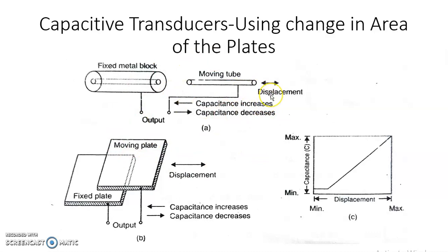As seen in the diagram, we are measuring the physical quantity displacement in terms of change in capacitance. In the first case, the parallel plates of the capacitor are in the form of metal tubes — one metal tube contains another, with a dielectric medium in between. As the inner metal tube is moved inside, the overlapping area increases and therefore the capacitance increases, allowing displacement to be measured.